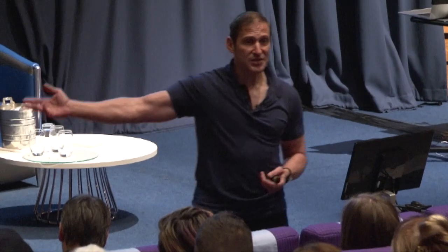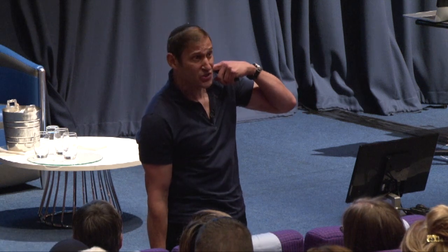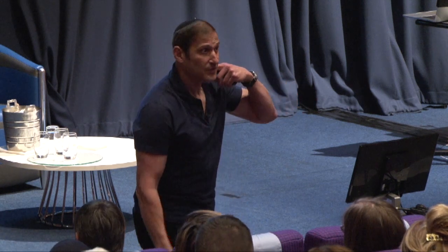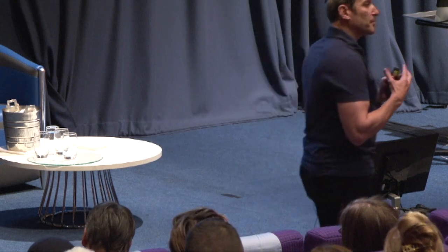Do you understand? Now I need to know your body habitus, your height. I wasn't kidding about the achondroplastic dwarf. If I'm scanning the ankle of an achondroplast, I may be exposing this abandoned lead to massive amounts of gradient. Do you understand? If it's a 7'3" basketball player, 2+ meters, and I'm doing a knee, do you really think I'm going to be worrying that he's got some coils inside his brain and a vagal nerve stimulator and I'm down there? I can't even focus that far away at my age. There's no single answer. It's your patient.